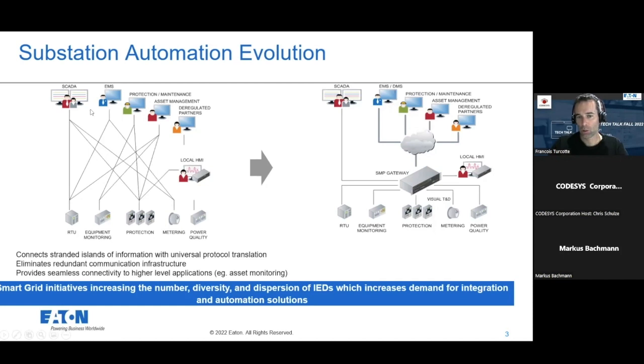In the past, people were just trying to access devices remotely through different paths with serial, TCP, any type of communication, which was kind of a mess, like a spaghetti, as you can see there on the left. But the evolution over maybe the last 10, 15 years has been that people want to separate those two layers and have the SMP gateway, or maybe another type of RTU, that is accessible and can interact directly from a client perspective. For example, SCADA, EMS, DMS. If there are any other parties that want to access data from the substation, they can now directly connect to the SMP or an RTU to gather that information.